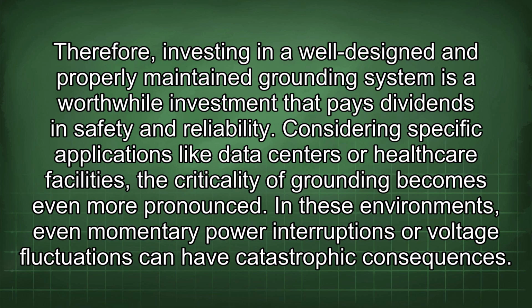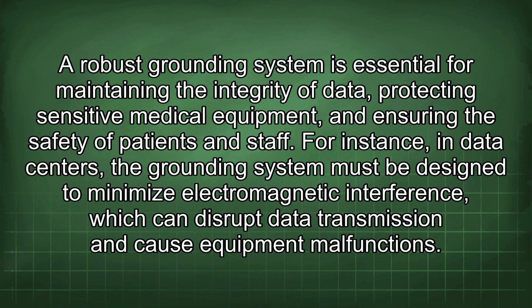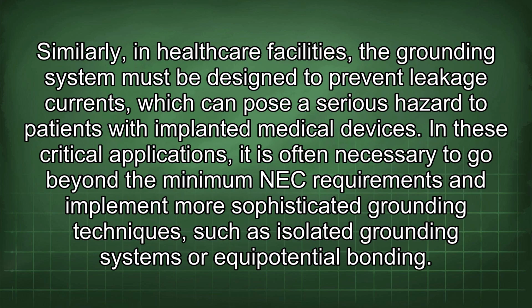Considering specific applications like data centers or healthcare facilities, the criticality of grounding becomes even more pronounced. In these environments, even momentary power interruptions or voltage fluctuations can have catastrophic consequences. A robust grounding system is essential for maintaining the integrity of data, protecting sensitive medical equipment, and ensuring the safety of patients and staff. For instance, in data centers, the grounding system must be designed to minimize electromagnetic interference, which can disrupt data transmission and cause equipment malfunctions. Similarly, in healthcare facilities, the grounding system must be designed to prevent leakage currents, which can pose a serious hazard to patients with implanted medical devices.